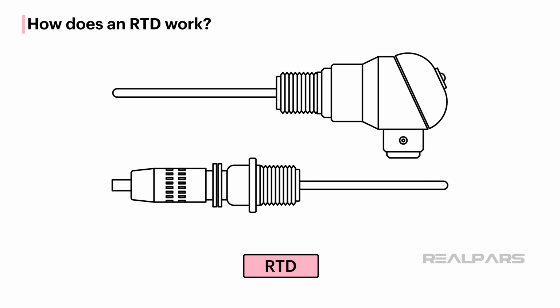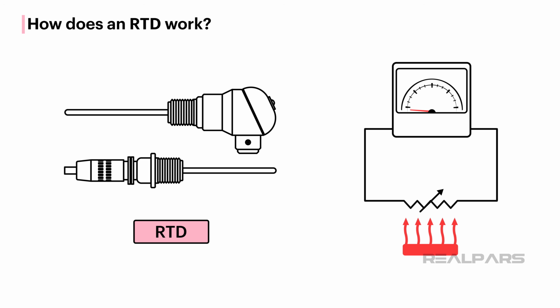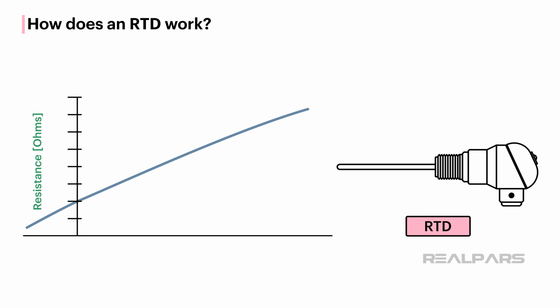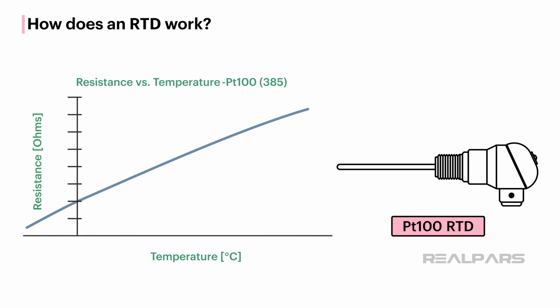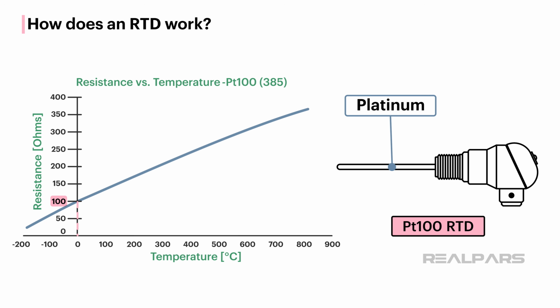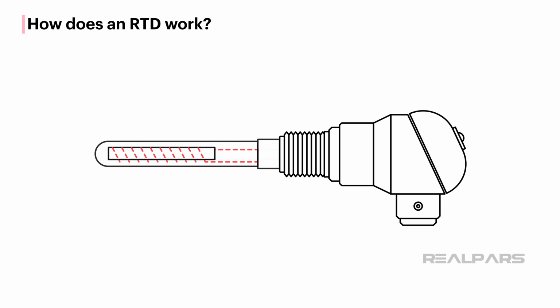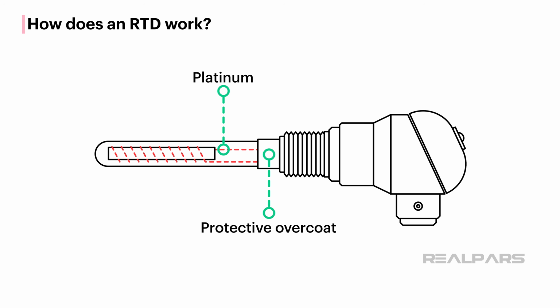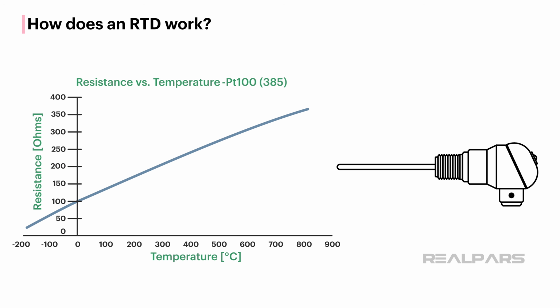An RTD is a passive resistive device made from a metal that changes resistance with a temperature change. If the temperature increases, the RTD resistance increases. RTDs are made with several different nominal resistance values at a specified temperature. For example, a PT100 RTD is made from platinum and has a nominal resistance of 100 ohms at 0 degrees Celsius. The actual RTD material is housed in a protective overcoat. So, if we measure the resistance of a PT100 RTD, we should be able to determine the temperature around it.